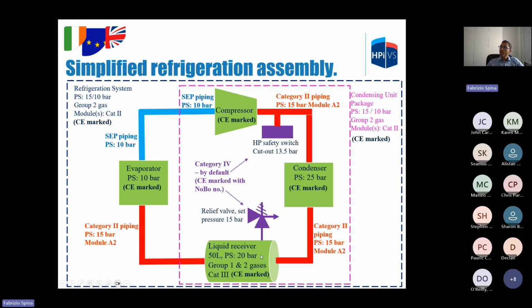The high side is fitted with a 15 bar pressure relief valve, so we can evaluate the category of this receiver, which is typically the highest category in the assembly, using the value of 15 instead of 20. So this assembly could be category 3, but if we check the category of the receiver using as PS 15 bar, as operating fluid gas group 2, since it is suitable for both group 1 and group 2, we use 15 bar group 2. This liquid receiver can be classified as category 2 instead of 3. So the whole assembly falls into category 2.